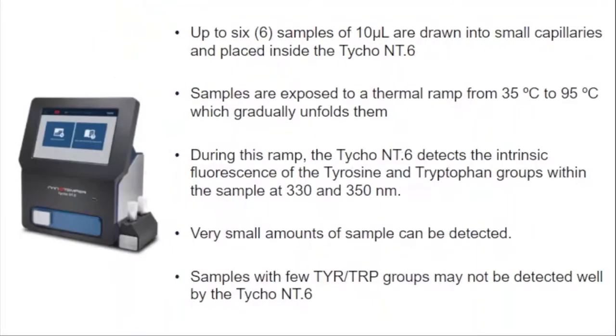So what is Tycho NT.6 and how does it work? The Tycho NT.6 can use up to six samples of 10 microliters. You draw them into small capillaries and place them inside the device. Those samples are exposed to a thermal ramp from 35 degrees Celsius to 95 degrees Celsius, which slowly unfolds them. While this ramp is happening, the Tycho NT.6 detects the intrinsic fluorescence of the tyrosine and tryptophan groups within those samples at 330 and 350 nanometers. It's worth noting that this relationship is dependent upon the number of tyrosine and tryptophan groups in the protein, so samples that do not have many of these groups may not be detected well by the Tycho NT.6.